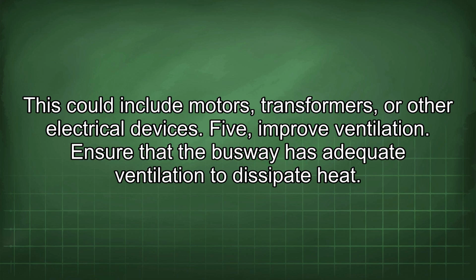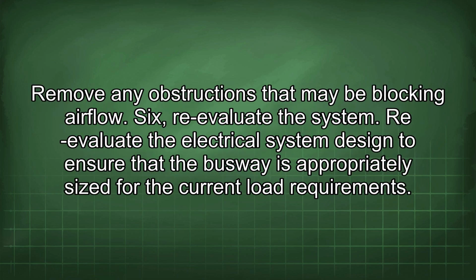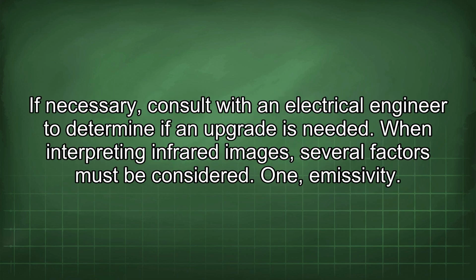5. Improve ventilation. Ensure that the busway has adequate ventilation to dissipate heat. Remove any obstructions that may be blocking airflow. 6. Re-evaluate the system. Re-evaluate the electrical system design to ensure that the busway is appropriately sized for the current load requirements. If necessary, consult with an electrical engineer to determine if an upgrade is needed.